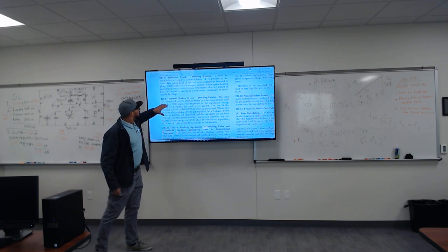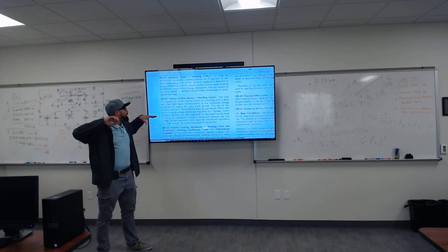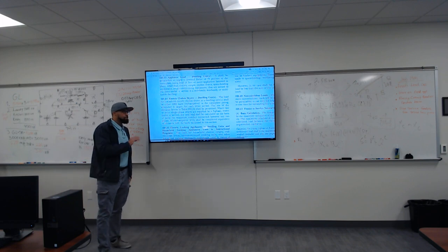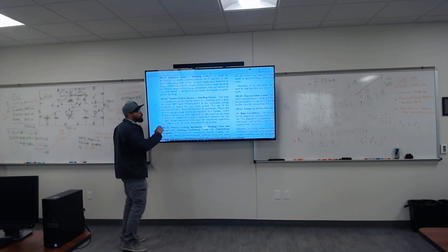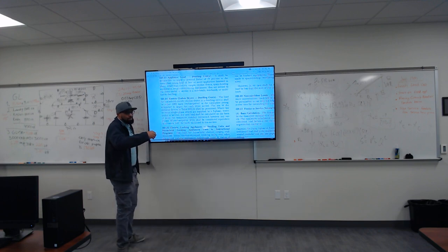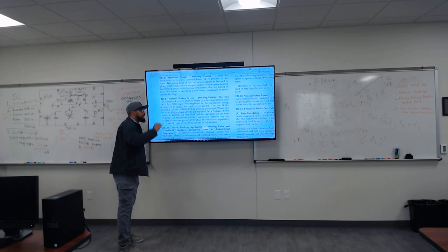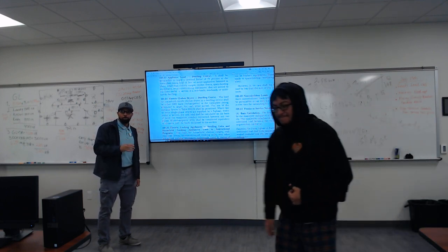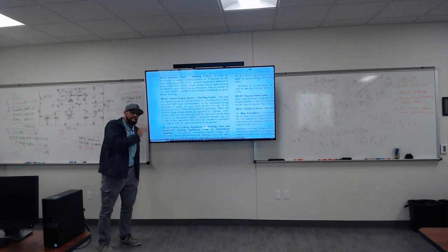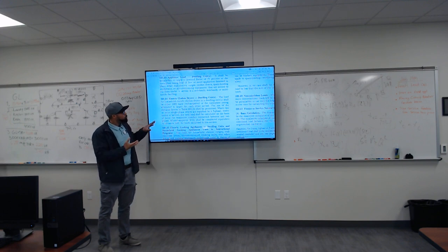All right. The load for a household electric dryer in a dwelling unit shall be rated at 5,000 watts or the nameplate rating, whichever is larger. For example, let's say you got one of those stackable dryers, and they're probably rated at 3,200 watts or 3,500 watts. The NEC says for calculation purposes, it has to be 5,000 watts. Or if the nameplate on it is more than 5,000, let's say if it's 5,500, you use the number greater than, but do not go less than 5,000 watts when you're calculating. The whole reason why we're calculating is to properly size our conductor, so we won't undersize our conductor and burn up stuff, all right? That's the whole purpose of Article 220.